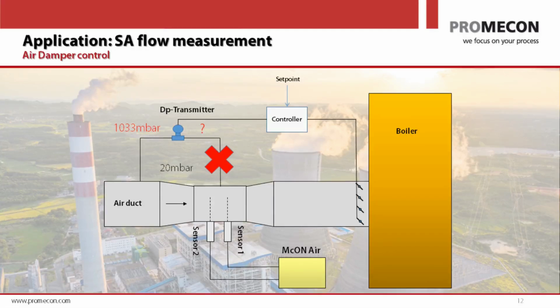And the problem is the fly ash that I just mentioned. The fly ash tends to clog the impulse lines that are needed to transport the pressure from the duct to the dP transmitter. So you can see these impulse lines, one for the static, one for the dynamic pressure, and just assume that one of these impulse lines gets blocked. Why do they block? The ash creeps into the impulse lines over thousands of hours. The ash can get pozzolanic. The ash can fill up this impulse line and basically block the impulse line. It can block it so well that sometimes it is even blocking the complete pressure.